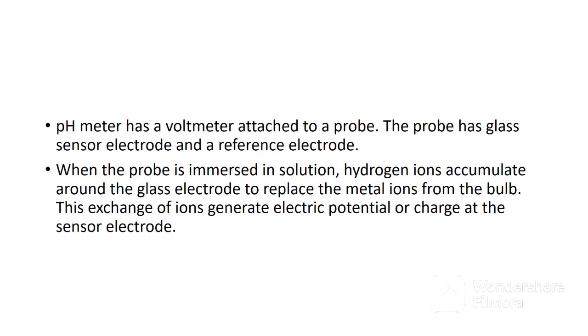The sensor electrode is designed to respond to changes in hydrogen ion concentration, while the reference electrode provides stable electrode potential. The sensor electrode is filled with a pH buffer, while the reference electrode is filled with potassium chloride solution. The sensor electrode bulb is coated with metal salts and silica, forming a porous glass membrane. When the probe is immersed in a solution, hydrogen ions accumulate around the glass electrode to replace the metal ions from the bulb. This exchange of ions generates electric potential or charge at the sensor electrode.